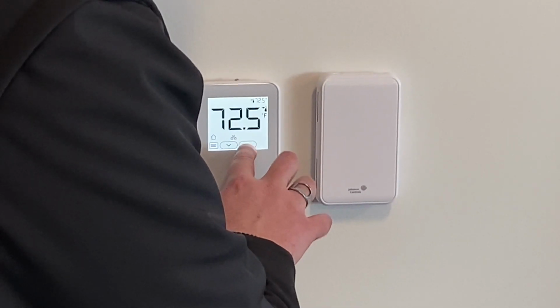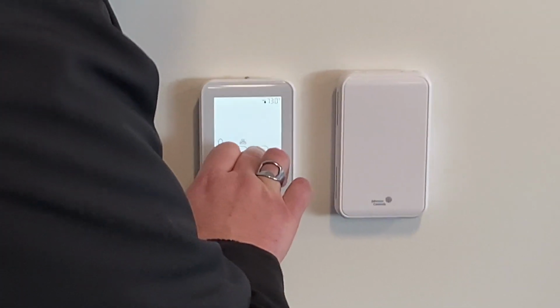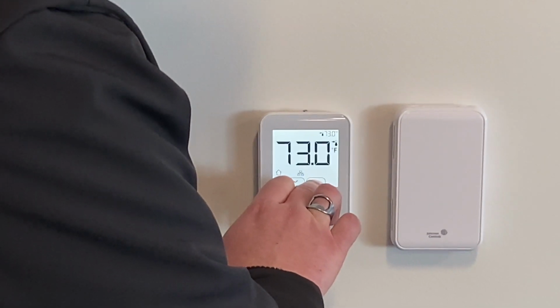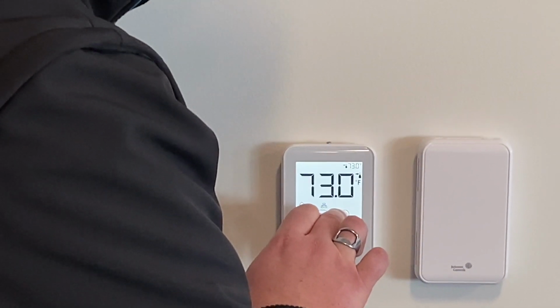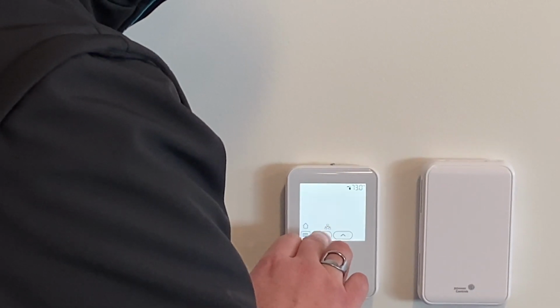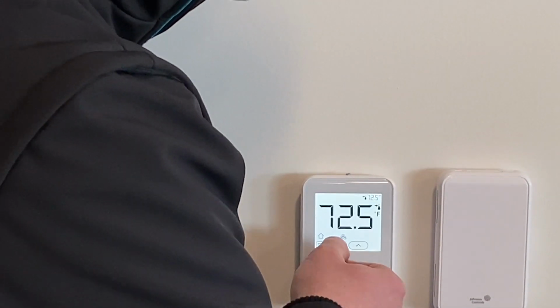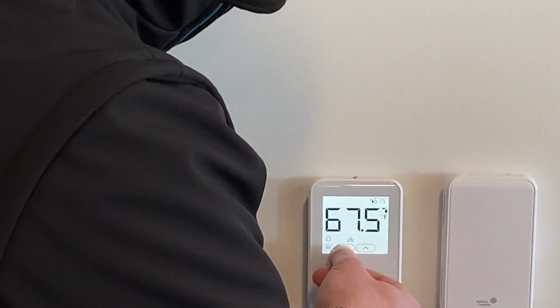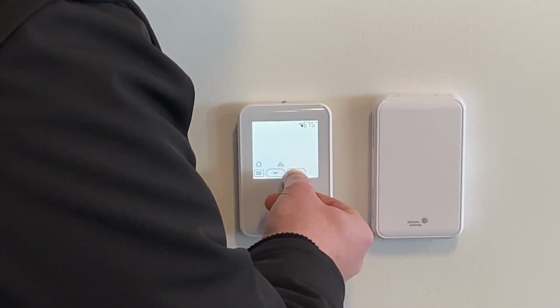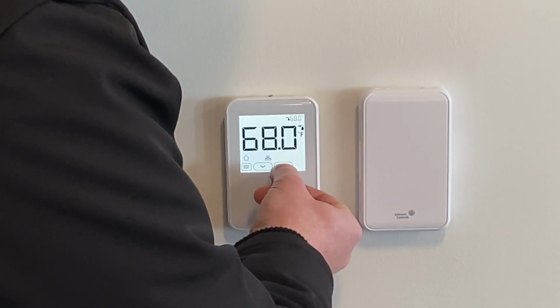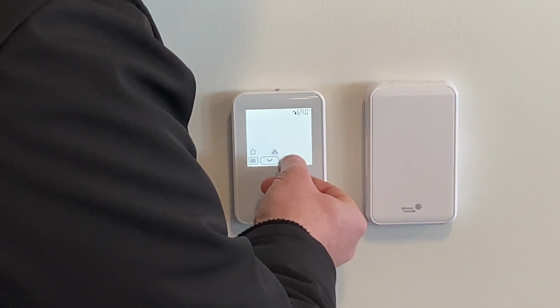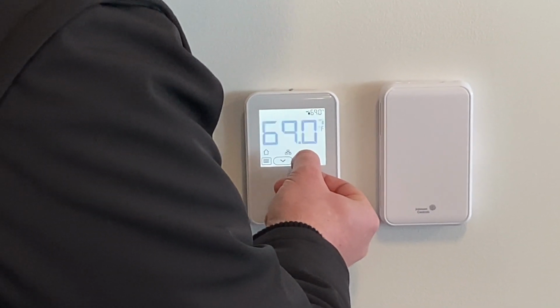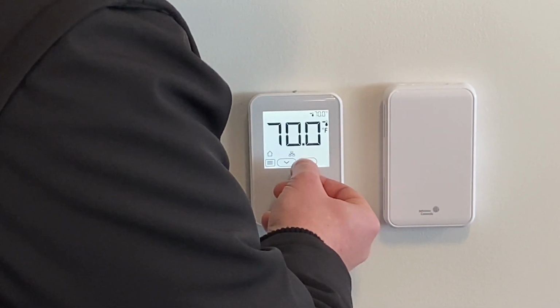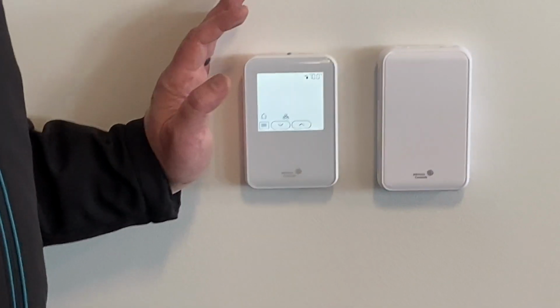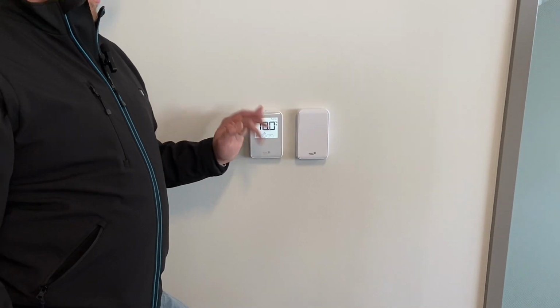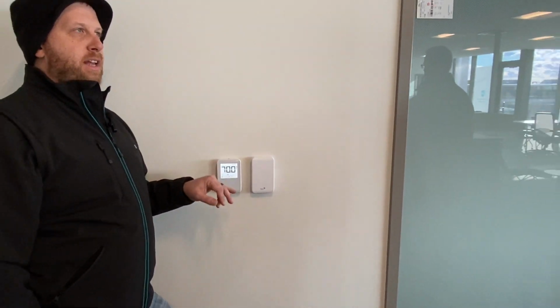Now I'm going to explain our set point range here in a little bit. You can see that's why I'm not a big fan of these. It might be 70. All right, it looks like it's 73. So we can go as high as 73 and I think down as low as 67. Okay, so I'm going to just go back to 70, keep it neutral. You're probably going to get a couple of complaints about these. Anyways, the way these work is just because they see a set point of 70 doesn't mean that the space will get to 70.